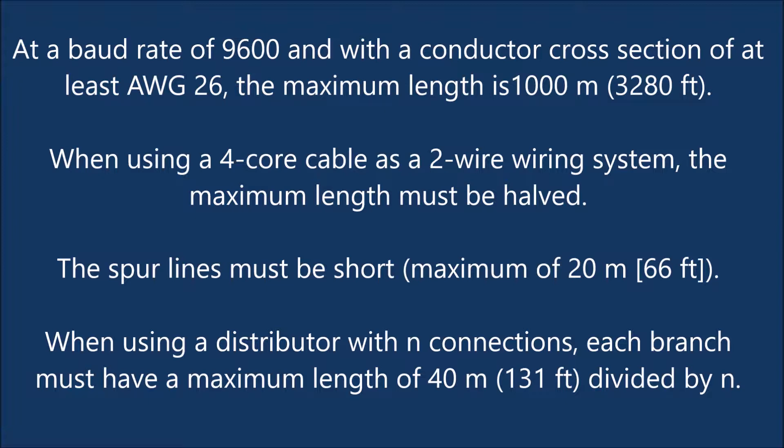The spur lines must be short — a maximum of 20 meters (66 feet). When using a distributor with N connections, each branch must have a maximum length of 40 meters (131 feet) divided by N.